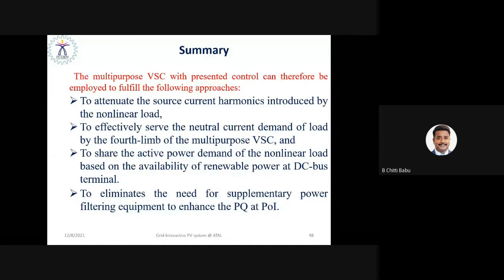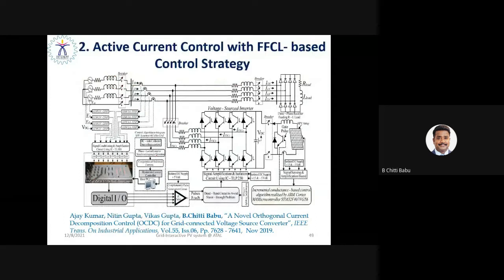It effectively neutralizes the neutral current with the fourth leg of the inverter, and moreover, it also contributes to active power sharing according to the load demand. So the frequency stability has been enhanced further. It also eliminates the need for supplementary power filtering equipment, so it doesn't need any other filtering or custom power devices to mitigate the power quality problem here. Hence the inverter is called a multifunctional inverter. If you have any doubt, please let me know.